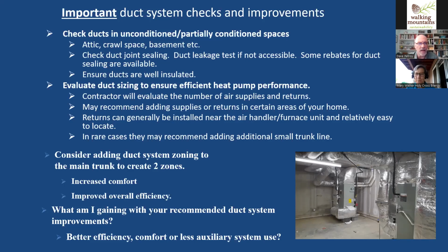First, the ducts in unconditioned spaces - crawl space, basement - need to be well insulated, especially with a heat pump, because the air temp isn't quite as warm coming out of it. You've got to have good insulation and make sure the ducts aren't leaking. If someone can't see the ducts in parts of the house, you might want a duct leakage test. There are also duct rebates available for duct sealing, often separate from the whole heating system rebates, so check into those with local groups. So what you've got to do is ensure the duct sizing.